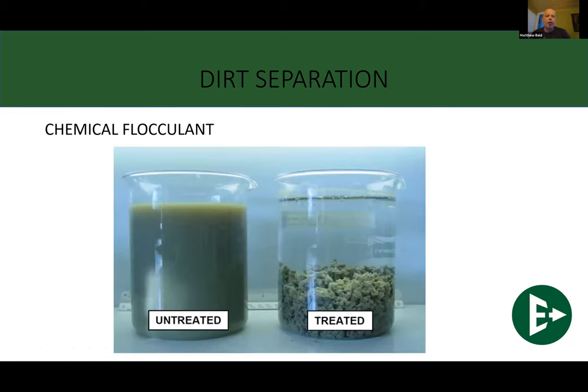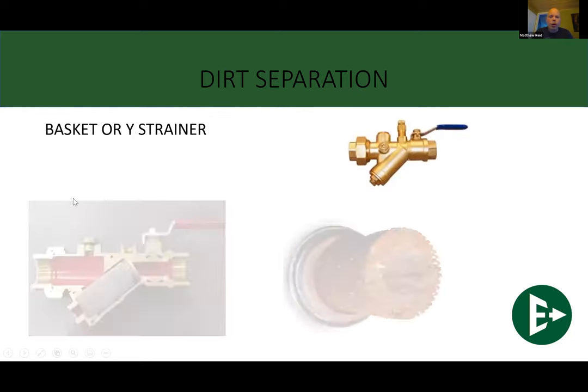So here's what the chemical additives do inside of a system. All that gunk inside of a system, usually it's ferrous particles or other microbials or something in there. It congeals them and brings them all together. So when you do a flush of a system after doing this sort of a treatment, you'll see a big amount of sludge come out, usually in the low point of a system. It makes it pretty easy to get the dirt out of a system. But if you don't have other pieces in place, you can just get that dirt built right back up again. It does make it for an easy one-time flush, though. So there's nothing wrong with doing this type, for the most part, if you want to do this every single time by adding new chemical into your hydronic system. Then there is your Y strainer.